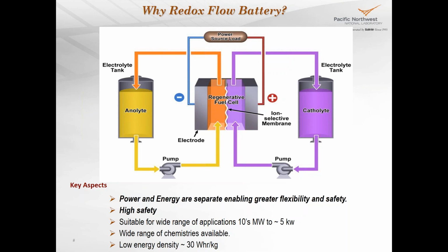They're nearly suitable for a wide range of applications, from kilowatt to megawatt hour, and there are several chemistries to choose from. However, the redox flow battery also has lower energy density, normally around 15 to 50 watt-hours per liter. For lithium-ion battery, those are much, much higher energy density, beyond 200 watt-hours per liter. So normally the redox flow battery requires a large footprint, while the lithium battery has a much smaller form factor.